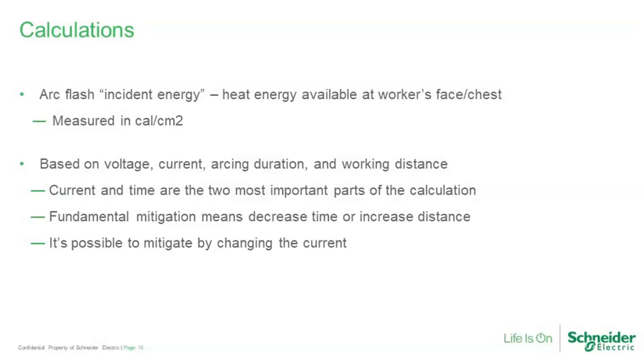Of course, voltage times current equals power. Power times time equals energy. So we go to the third thing, the arcing duration: how long does the fault actually last before the breaker opens, the fuse clears, or whatever happens to make the arc go away? And then finally, the last primary quantity is working distance. The farther you move away from the arc, the less energy you're exposed to.